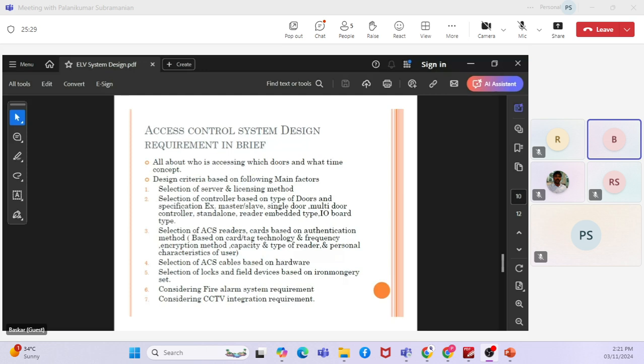So we can specify the time in the programming software, within this particular time to that particular time. Let's say for office hours only the employees are allowed. So we specify the time and we specify the doors also. For example, server and IDF doors and control room doors. Not all people can access those doors, so we can make an access privilege for each user. The common doors can be accessed by all people, and some specific critical doors only by a particular level of people. And based on timing, within this time all the employees can access, and out of office hours cannot enter. This can be applied for all kinds of buildings and premises.